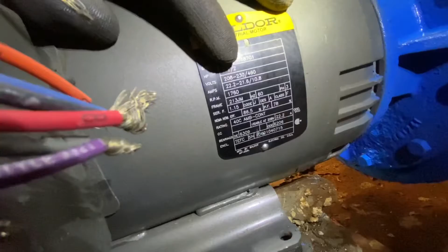So what you have to do is look at your nameplate and see it says 208, 230 / 460. So in this case, 208, 230 is your low voltage, 460 is your high voltage. All right. So notice you've got some numbers here. So we're dealing with the high voltage. I know it's 480 because the last one was 480, right?